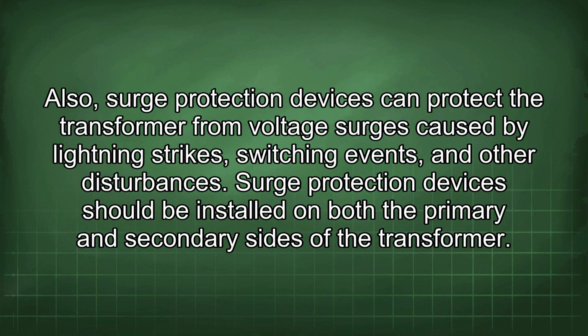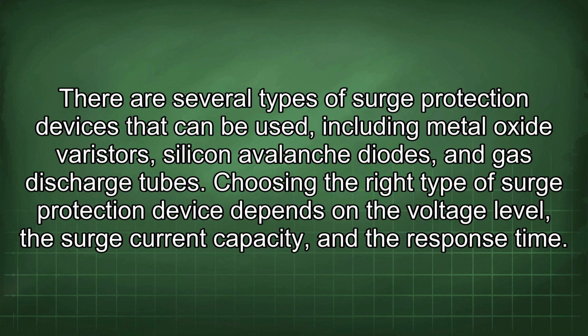Also, surge protection devices can protect the transformer from voltage surges caused by lightning strikes, switching events, and other disturbances. Surge protection devices should be installed on both the primary and secondary sides of the transformer. There are several types of surge protection devices that can be used, including metal oxide varistors, silicon avalanche diodes, and gas discharge tubes.